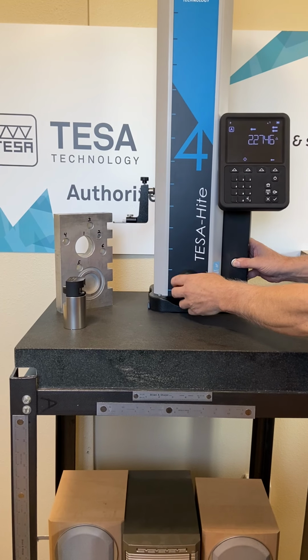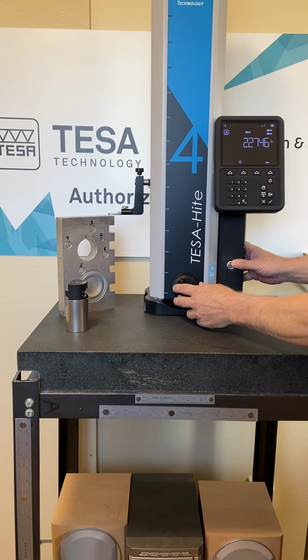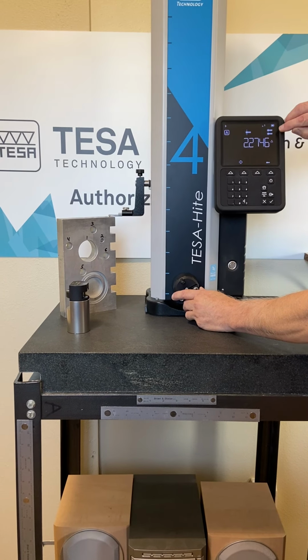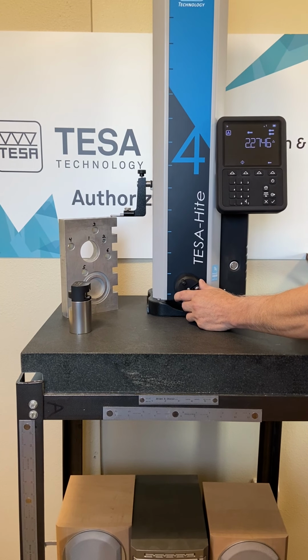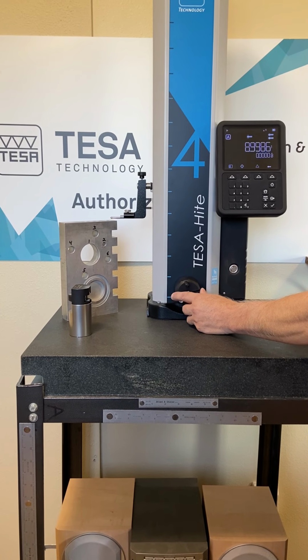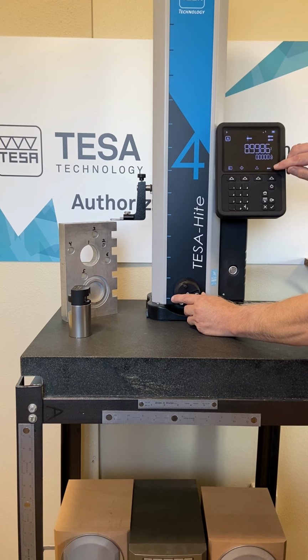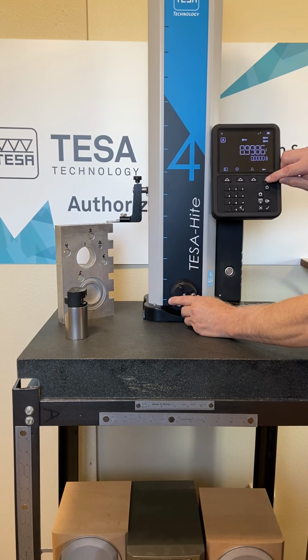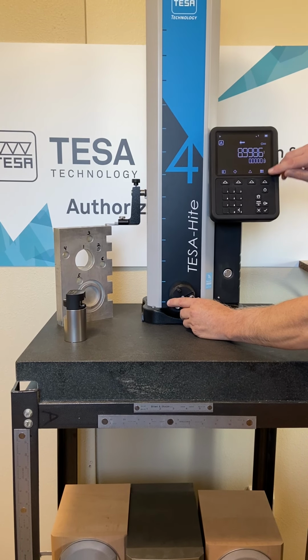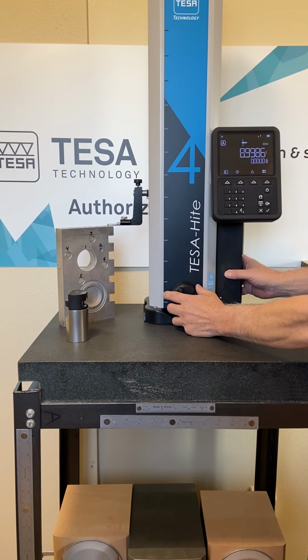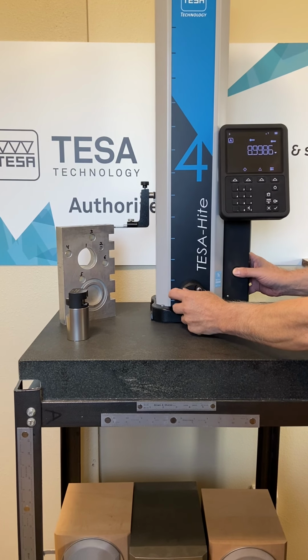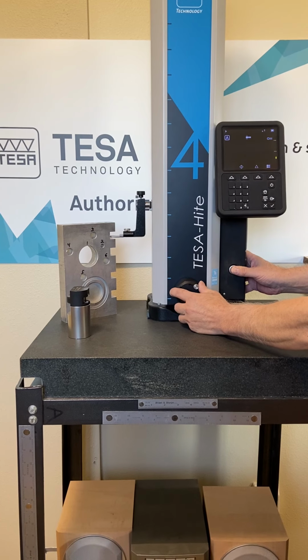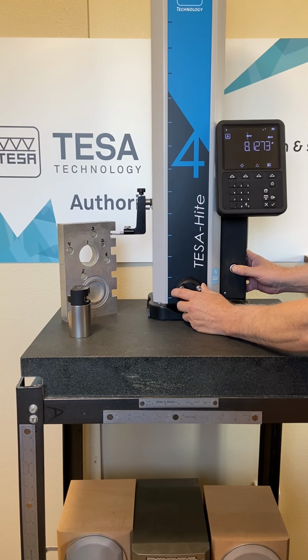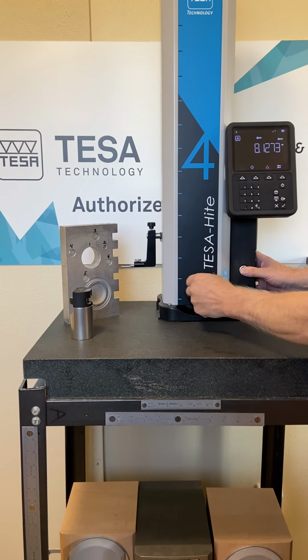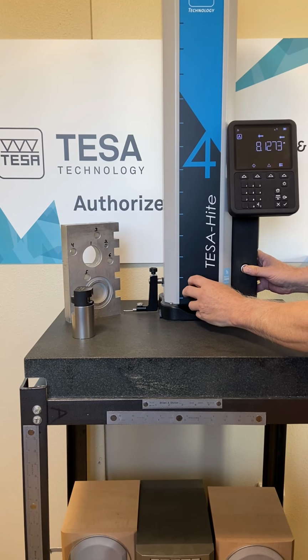If I want to go up to the top and take a simple point-to-point measurement, I've got 2 probes showing on my display, so I can either hit it twice to take a measurement, or my probe symbol is right there. I can hit that function key, and now I've only got 1 probe showing on my display. So I only have to hit it once to take a measurement, and now I can take a top, an upward or downward measurement. Go back down here at the surface plate.